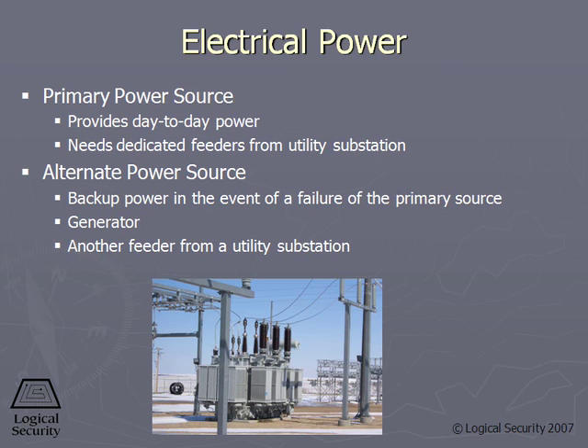All buildings have a primary power source. This is on the standard power grid, and this is the default connectivity that you have to the power substation. This is typically our main source of power in a building. However, if we need to ensure that our systems remain active, even in the case of power failure, very often what companies should do is pull dedicated power lines from a different power substation. In case one substation fails, I can draw power from the alternate power substation.